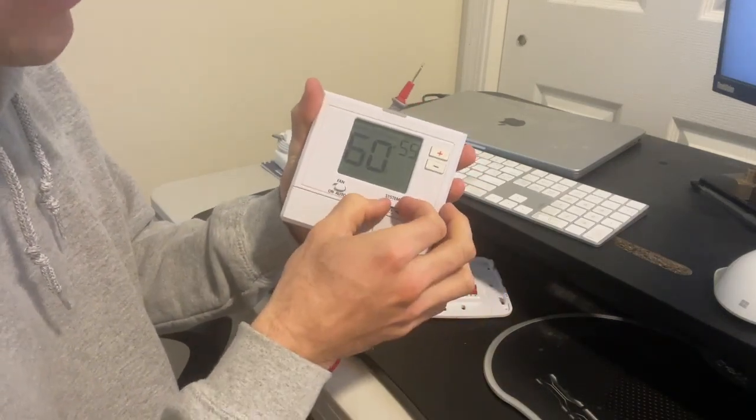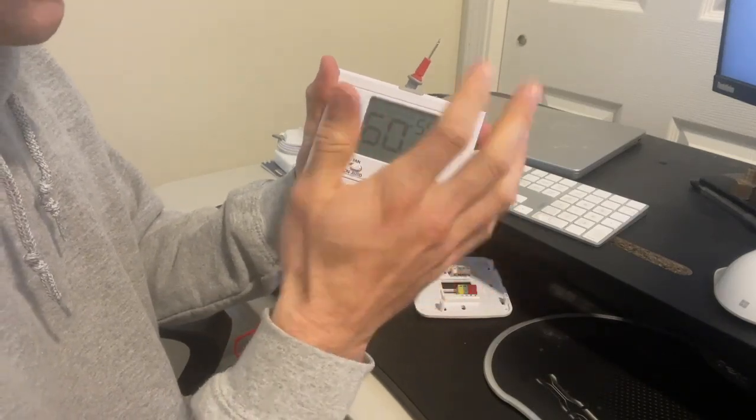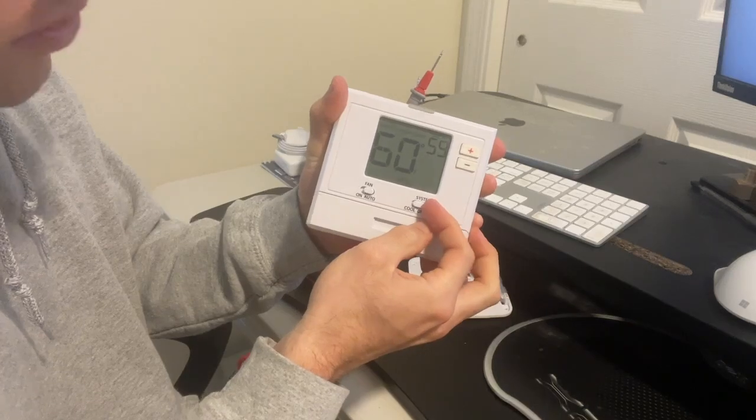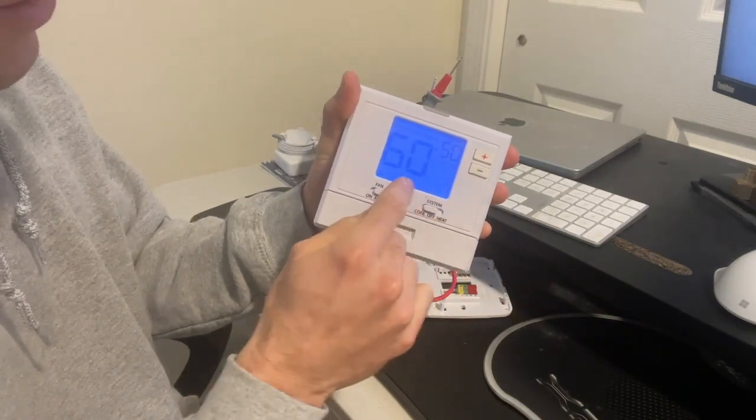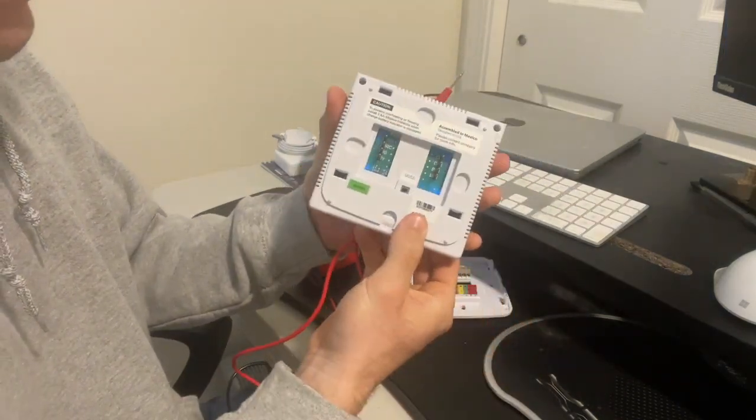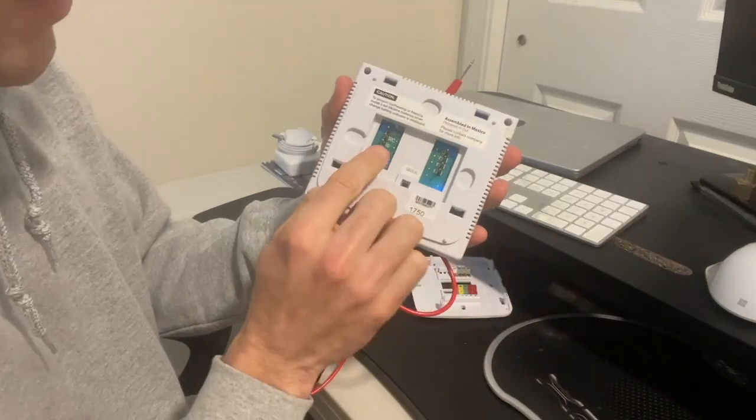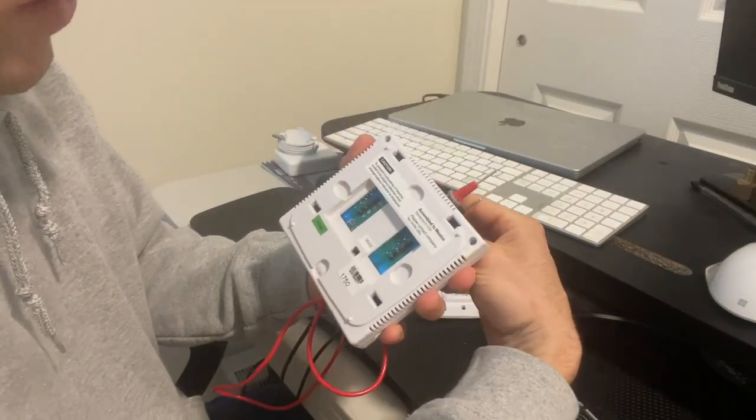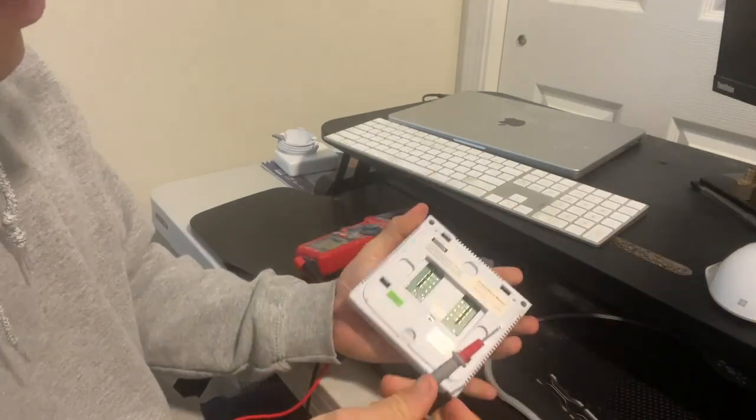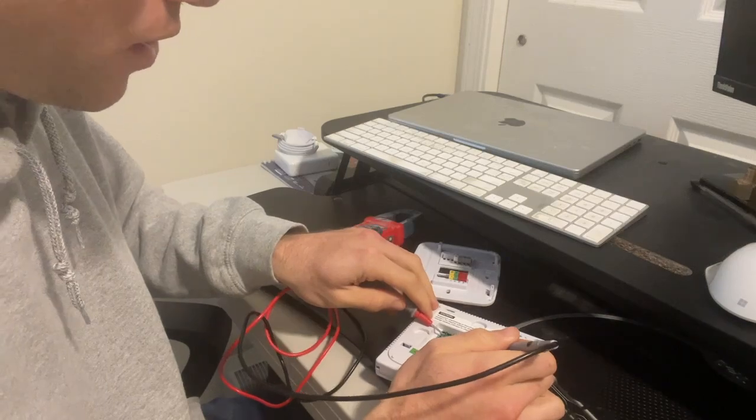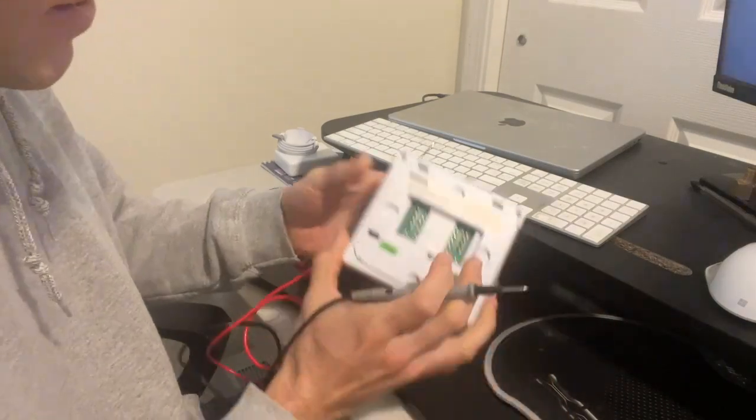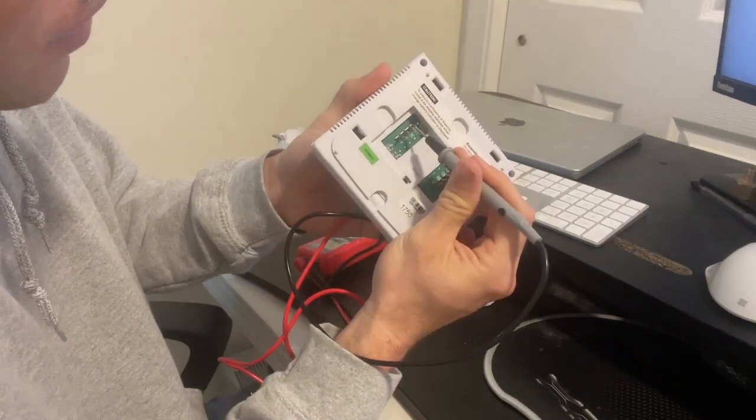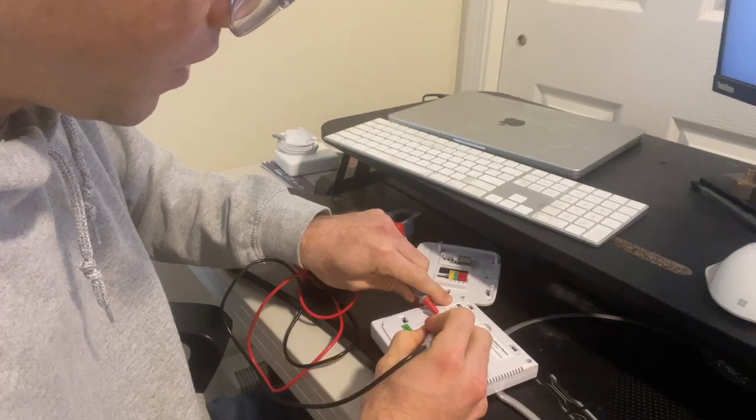So the other thing we can check is the cooling mode. So if I set this to cooling right now and I have my set point temperature at 50, the current temperature is 60, what I expect to see is if I go to the back of this thing, I see an RC and a Y. And so I should expect to see a circuit between these two, a continuity between the two. So I'm connecting the first one to RC and Y. So what I'm seeing is that connection made between RC and Y.